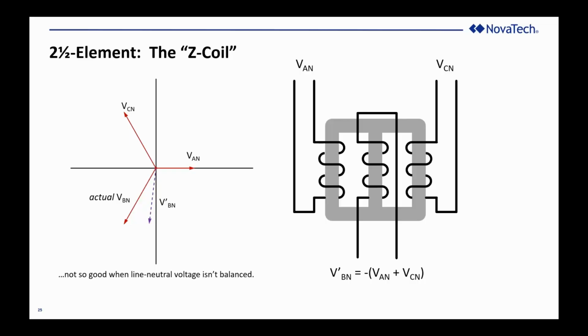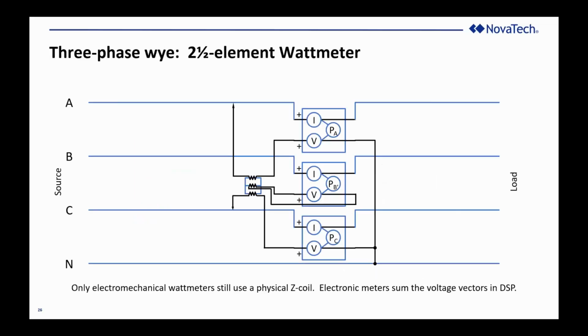And since you're up at 500 kV, 345 kV, 230 kV, you're in the transmission system, your source impedance is very low, and the expectation of voltage balance is fairly high. So in a case like that, when there wasn't an alternative to an expensive wound PT, a lot of utilities would use 2.5 element three-phase wattmeters on Y-connected transmission lines to save the cost of 1 PT. The meter itself, remarkably, is more expensive when you're talking about an electromechanical meter, because not only does it still have to have the 3 elements that you would have in a 3-element meter, but it also has to have this internal Z coil to produce the third voltage.